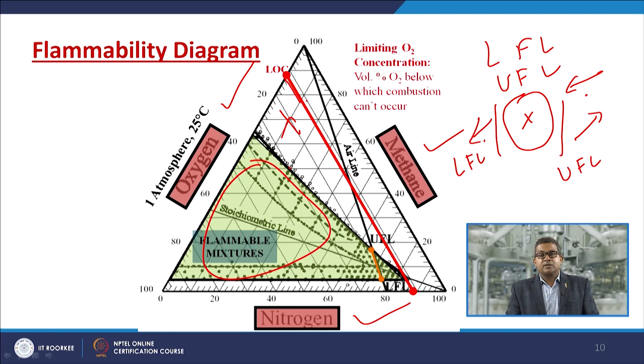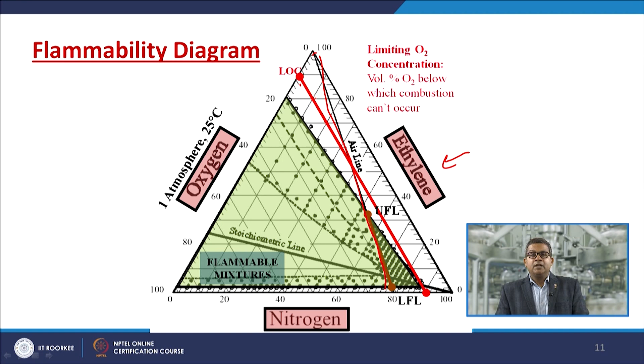Now here again you can see the LOC, and this is our air line, that means the supply of air. Oxygen is automatically being extracted from the air. So the combustion of ethylene requires this quantity of oxygen. So by any means of introduction of nitrogen, if you introduce a certain quantity of nitrogen, the limiting oxygen concentration is on the lower side, or the LFL is on the lower side, so that the mixture doesn't form a combustible one.